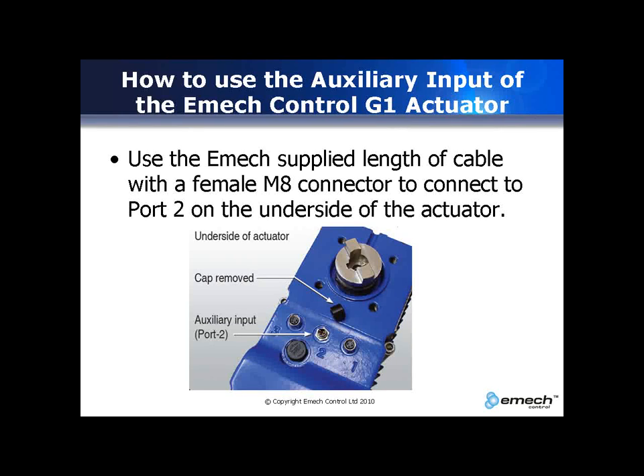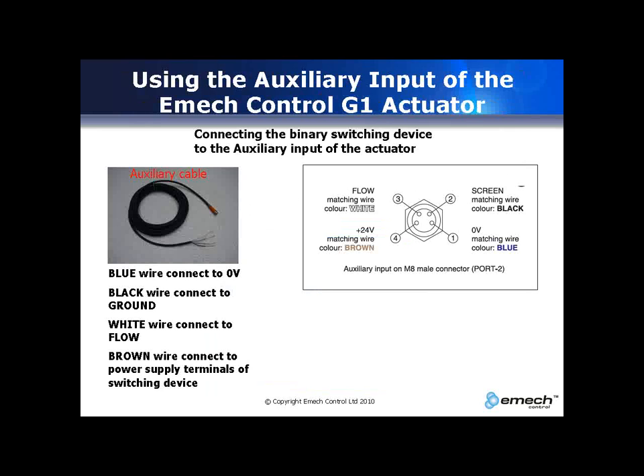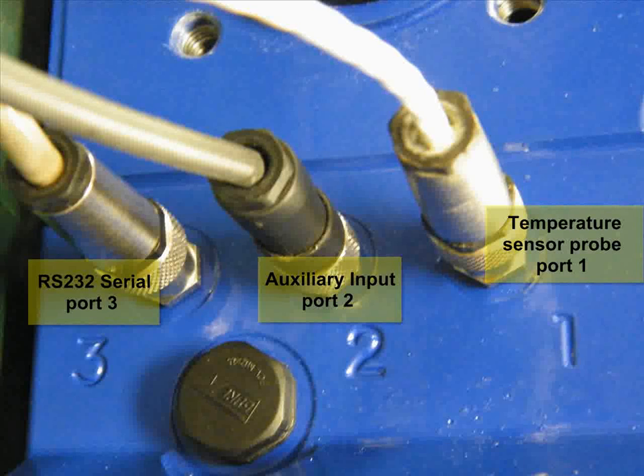Next, connect the supplied Emech auxiliary cable to the port number 2 on the underside of the actuator. The auxiliary input is a 4-pole M8 male connector that accepts a 5 to 24 volt configurable active low or active high signal. The switching device is placed between pin 1 and pin 3 of the connector. Pin 4 on the connector outputs 24 volts DC, which can be used to power the auxiliary device, but the device must not draw more than 100 milliamps. Also connect the supplied temperature probe to port number 1 on the underside of the actuator.